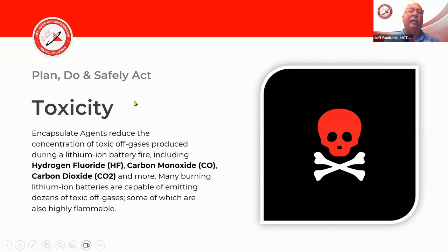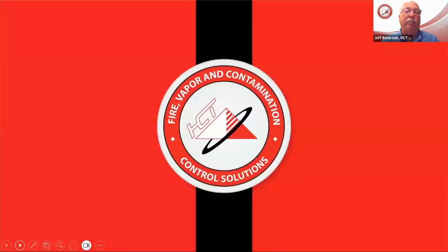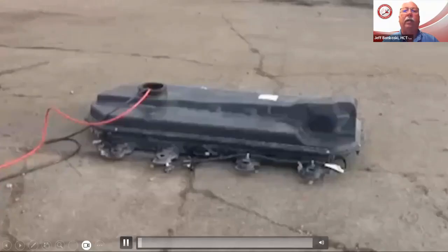We start looking at the ability of F500 to encapsulate. One thing it can do is encapsulate the hydrogen gas, as well as the smoke coming off the batteries, the hydrofluoric gas, the carbon monoxide, and the carbon dioxide. F500 is able to encapsulate and reduce the toxicity, greatly reducing the HF gas. We've got reports showing the amount of reduction F500 is able to cause when used on these types of batteries.